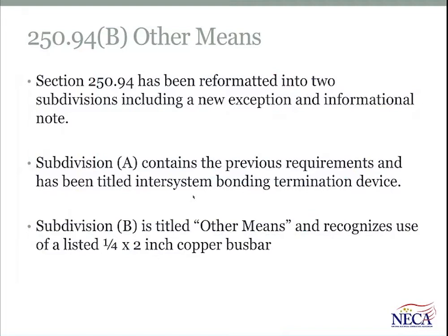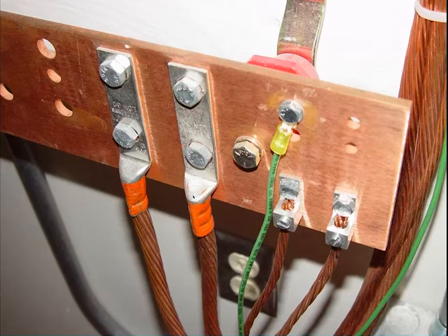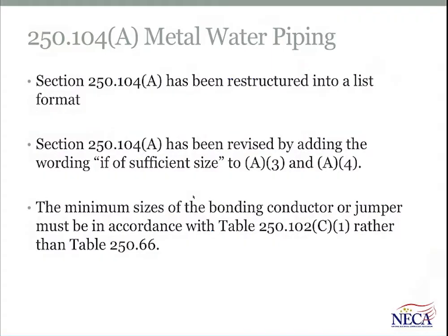Subdivision B recognizes other means, and a common other means that's used to accomplish a provision for communications, grounding, and bonding is a listed 1/4 by 2 inch copper bus bar that could be used in addition to an IBT. So if you had this type of arrangement installed for a communication system, it would be acceptable and now recognized in the 2017 NEC for use.